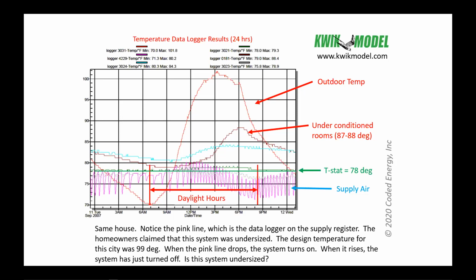Had this been in a humid climate, not only do you have temperature issues, but that short cycling reduces the air conditioner's ability to remove humidity, to remove moisture from the air. Not only will you get uncomfortable temperatures, you'll get very uncomfortable humidity inside this house. And then the tendency is to drop the set point down to like 70 degrees. Now, what are we doing? We're just running oversized equipment longer. We're wasting energy, we're putting stress on the grid and all that other kind of stuff. So it's very, very important. This is a classic example of oversized equipment.